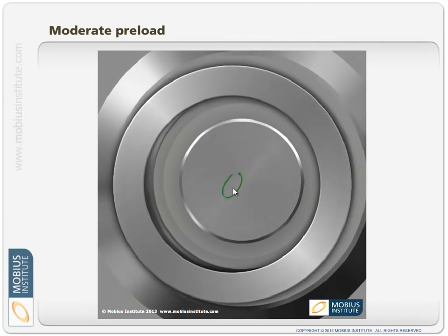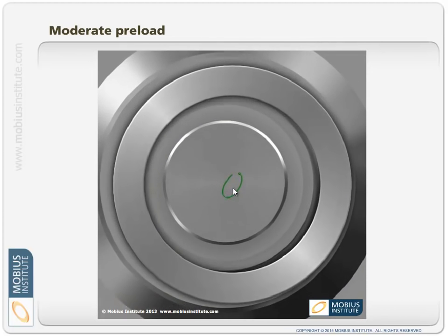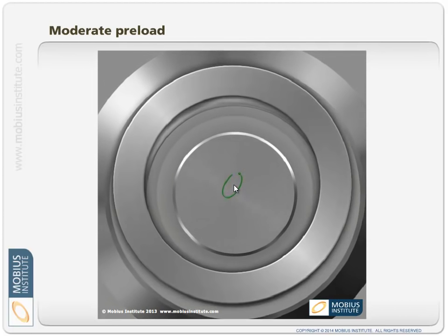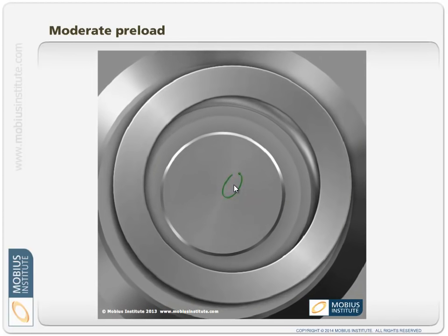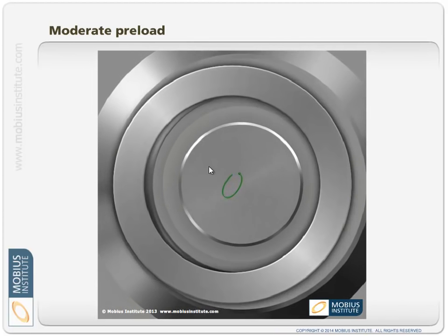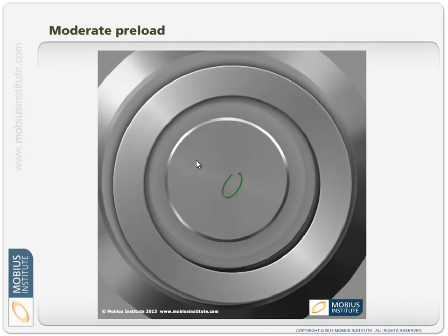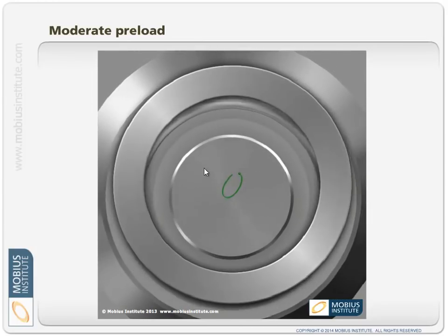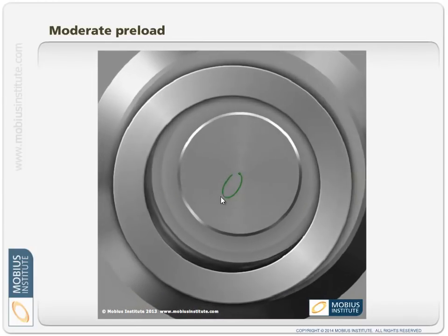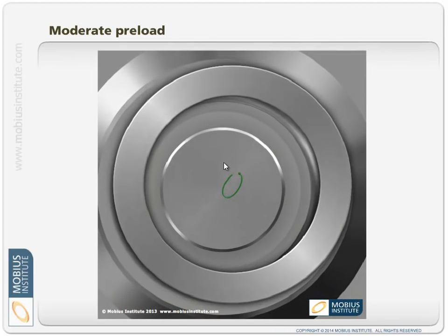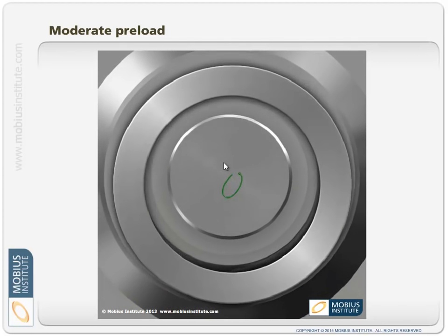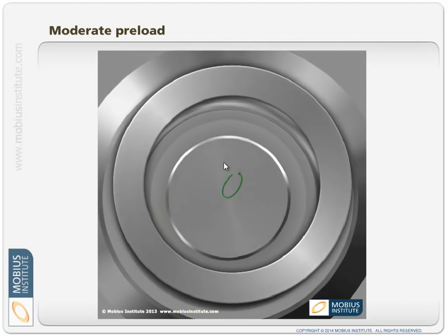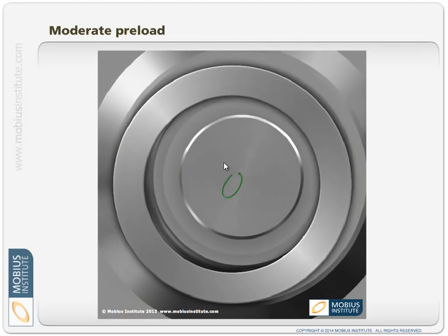That tells me that there's some sort of force doing that. It could be thermal reasons, it could be what the steam jets are doing, it could be misalignment, but you can visualize maybe that there's this force moving in the direction of my mouse, sort of coming down in this angle, and it creates that ellipse that we're seeing. The ellipse is just telling us what it's doing, where those probes are located, which is an important little thing. We only really know what's happening where those probes are located.